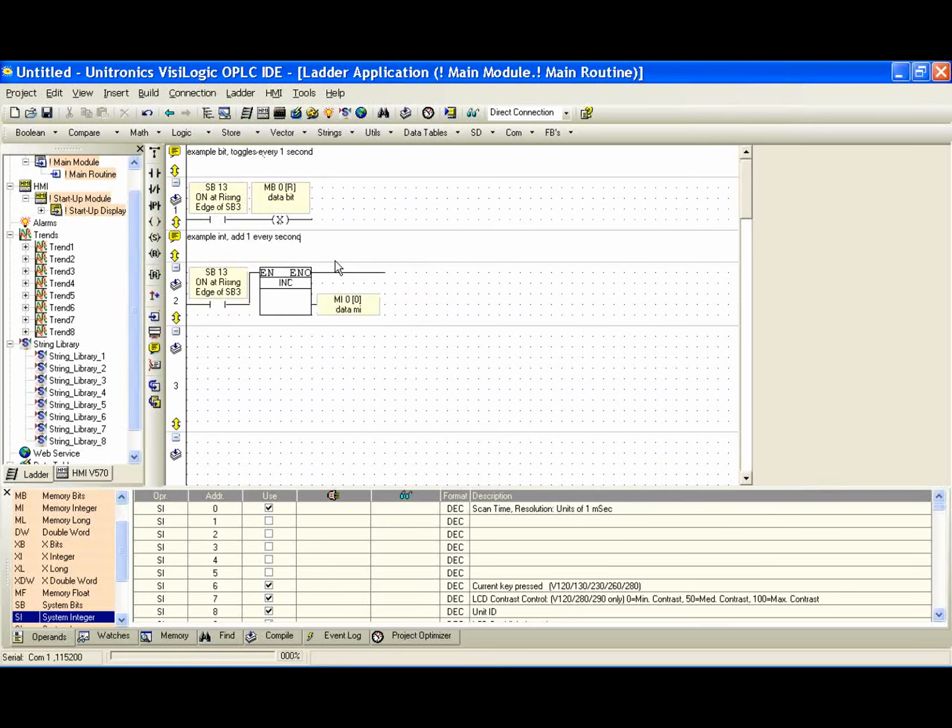Our third will be the memory long. You may ask here, what is this piece of data going to do, this memory integer, if we leave it on long enough? Well, we expect it to count all the way up to its upper limit, 32,767, and then on the next increment, it's going to go to value negative 32,768. And it's going to continue increasing from there. The idea is that when we reach the high limit and we increment a little more, we roll over. And if we leave it running long enough, we'll see that, but we probably won't here.